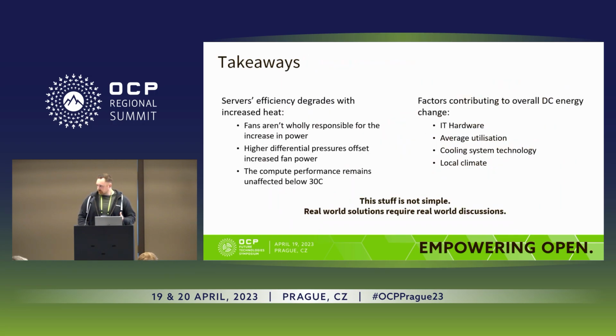So, key takeaway before we move to the Q&A: fans aren't entirely responsible for the hardware piece, as leakage current and differential pressure offset some of the impact, but not all of it. Basically, compute below 30 degrees, or in my view below 35 to 40 degrees, is completely unaffected, as is the failure rate. So raising temperature could be an incredibly good environmental initiative.